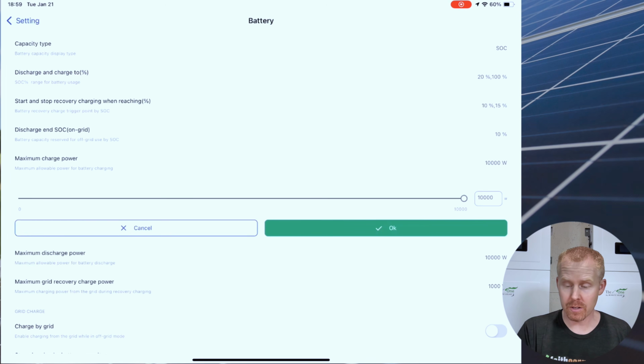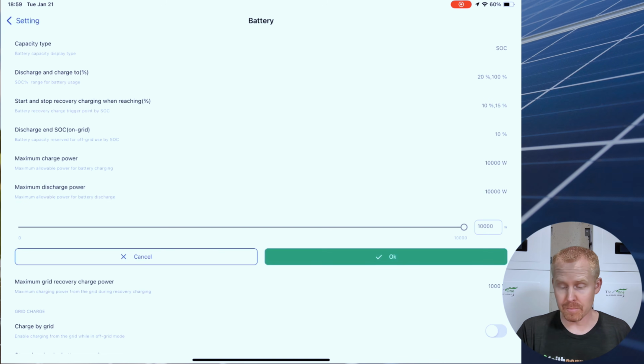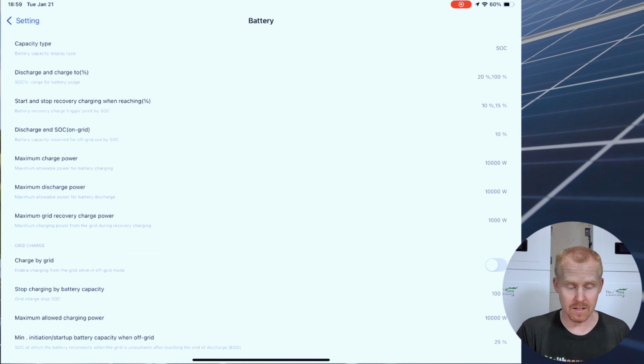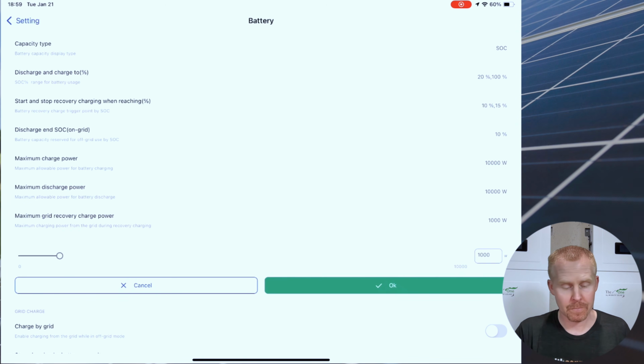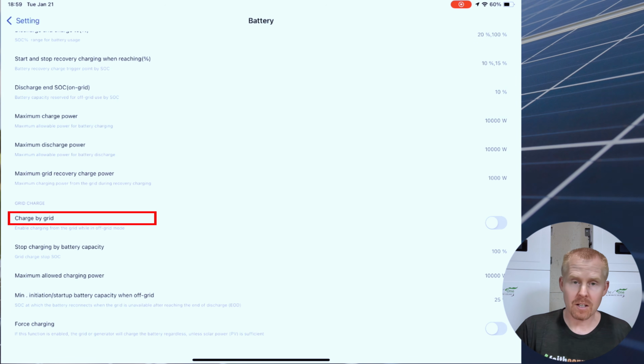Maximum charge power, 10,000 watts. Maximum discharge power, 10,000 watts again. Maximum grid recovery charge power. So that's how much power do you want to charge from the grid in the event that it ends up using that start and stop recovery charge a few lines above. The charge by grid toggle here, again, same thing we saw with the user settings.